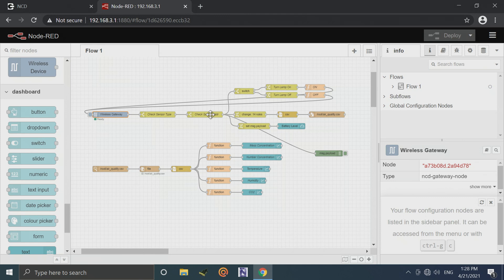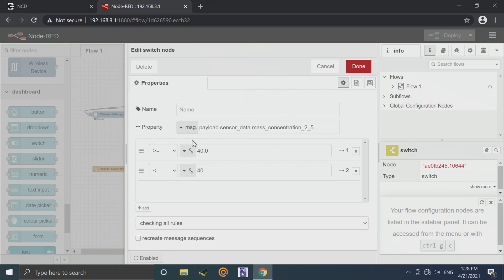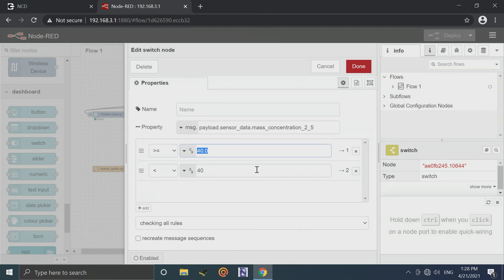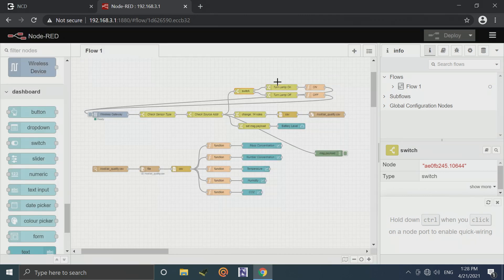It's also going to monitor the 2.5 particulate matter. Through this switch node, if the 2.5 concentration is greater than 40, it's going to come out the top connection. If it's less than 40, it's going to come out the bottom connection.